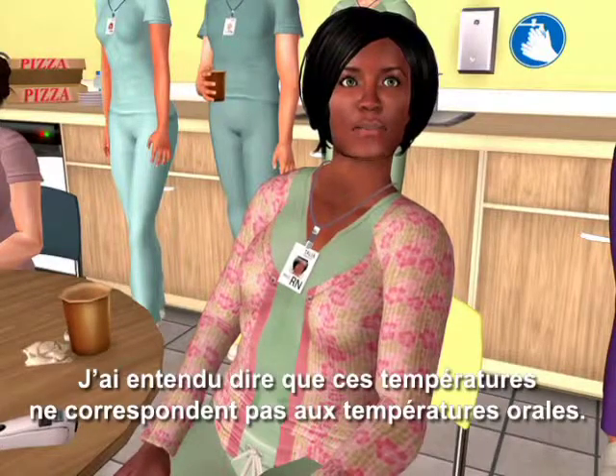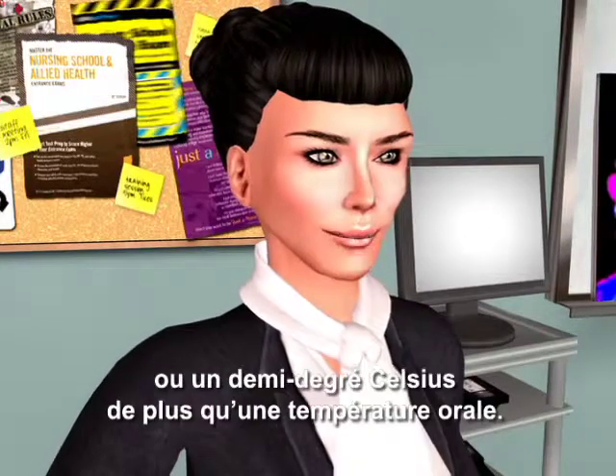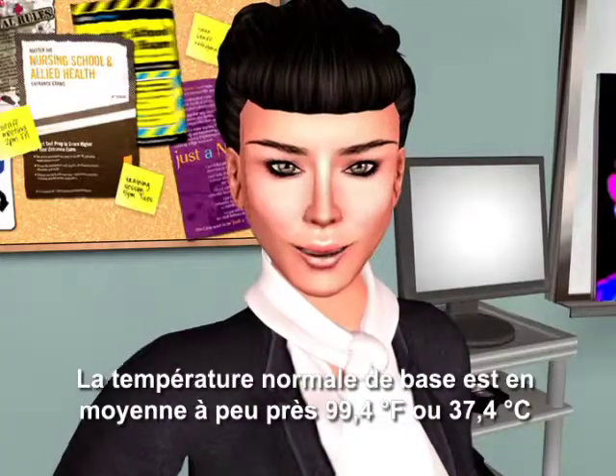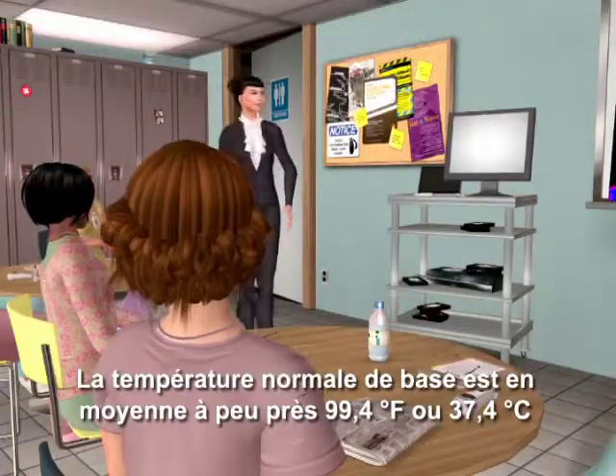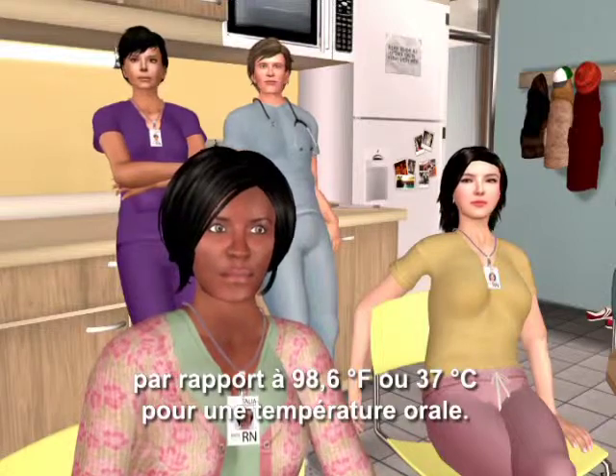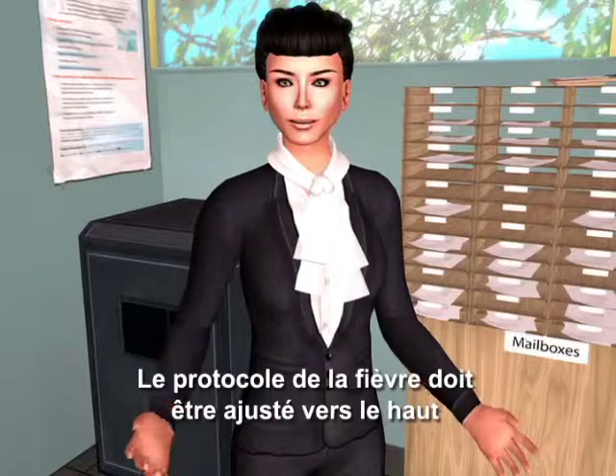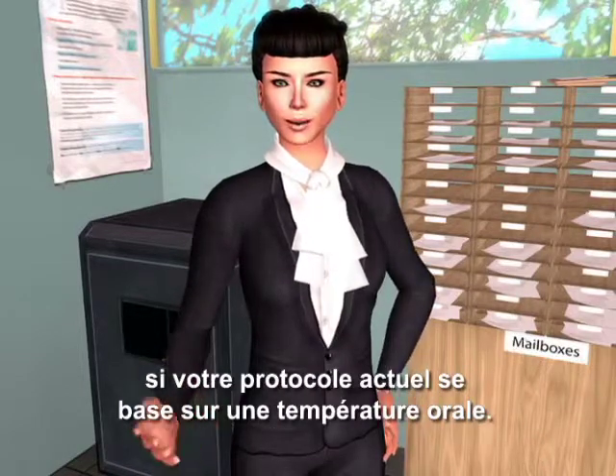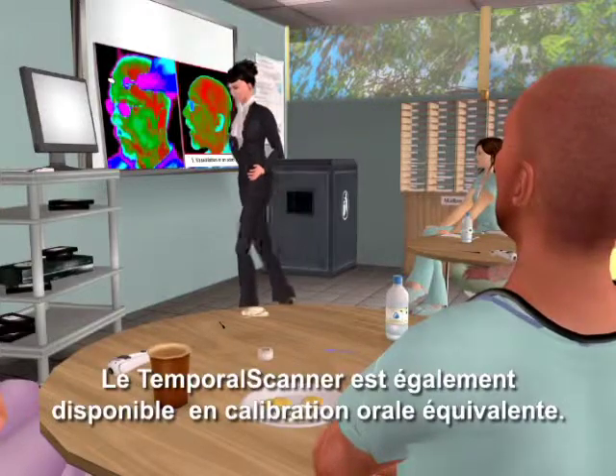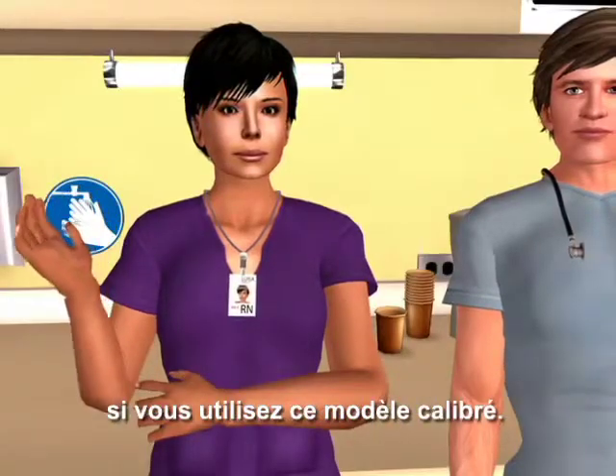I've heard the temperatures don't match oral temps. The temporal scanner is measuring core temperature, about one degree Fahrenheit or half a degree Celsius higher than an oral temperature. The mean normal core temperature is about 99.4°F or 37.4°C, versus about 98.6°F or 37°C for an oral temperature. Fever protocol will need to be adjusted upwards if your current protocol is based on an oral temperature. The temporal scanner is also available in an oral equivalent calibration, requiring no adjustment in the oral-based Fever protocol.